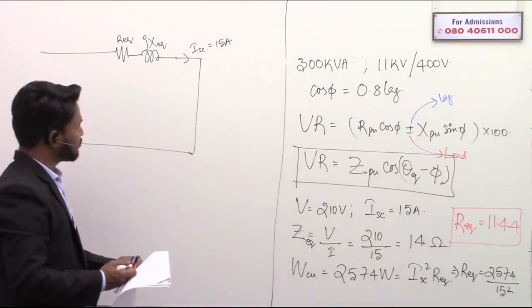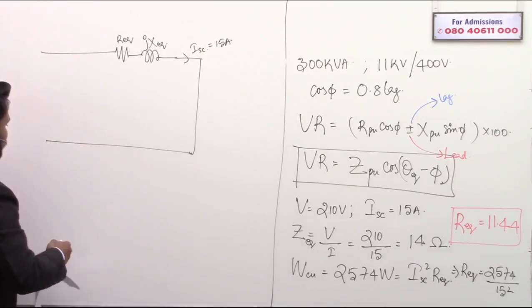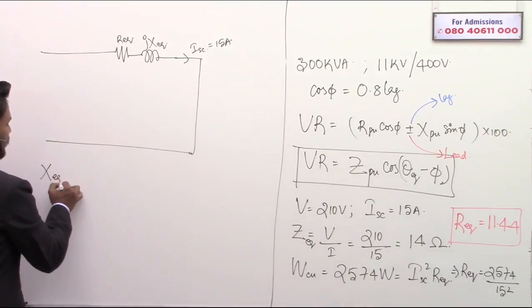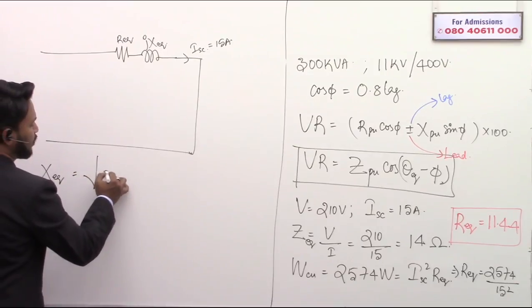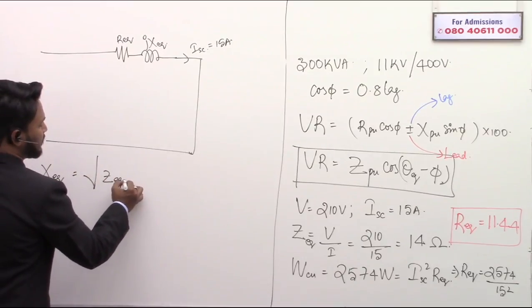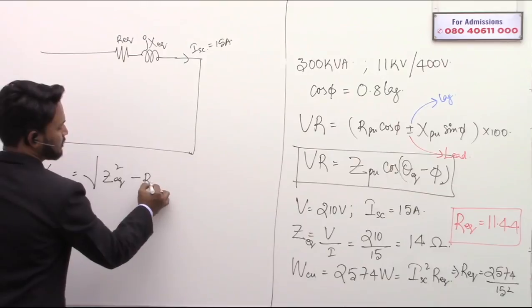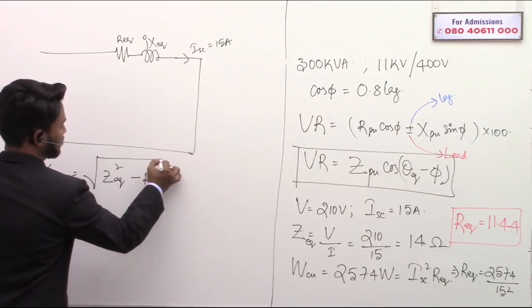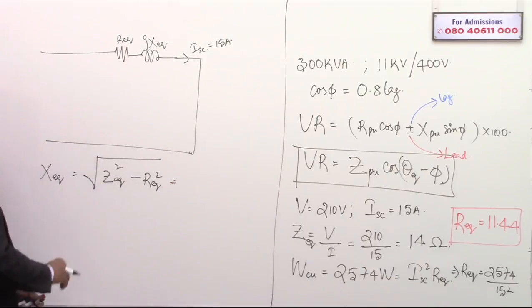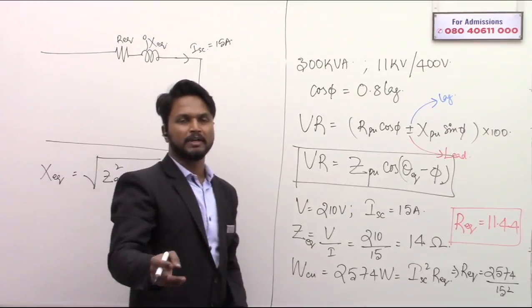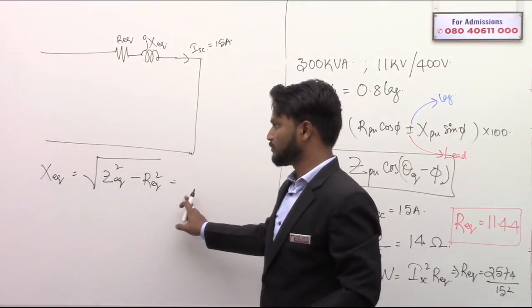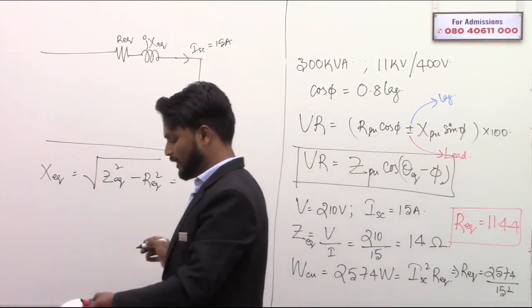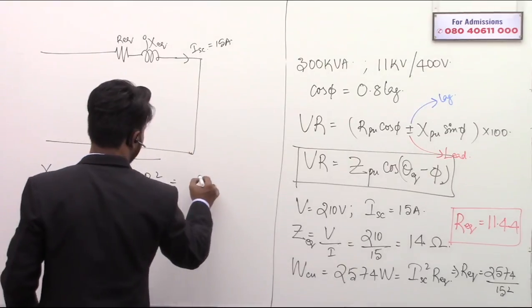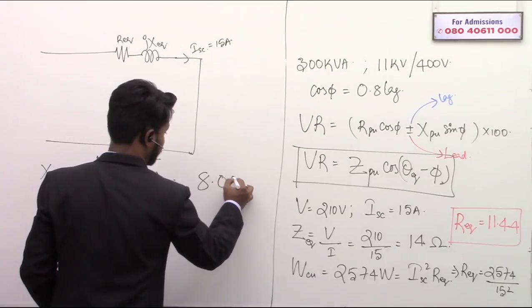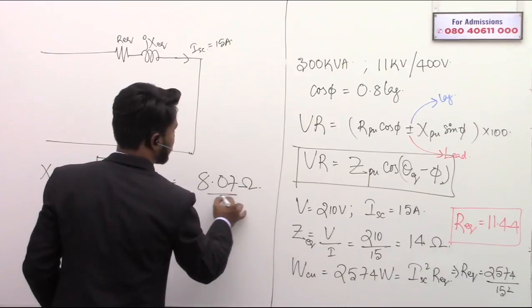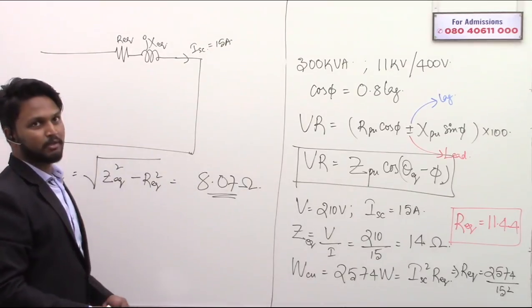If you need X equivalent, you can calculate that also. X equivalent will be equal to the square root of Z equivalent squared minus R equivalent squared, since Z equivalent is equal to the square root of X equivalent squared plus R equivalent squared. You can calculate in this way. X equivalent is equal to 8.07 ohms.